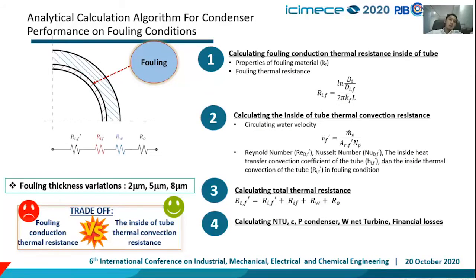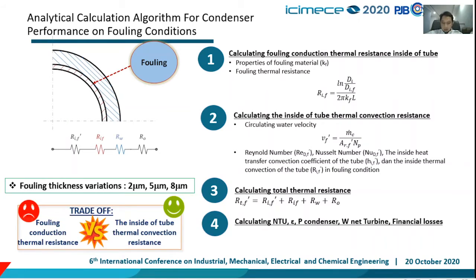This is the analytical calculation algorithm for condenser performance under fouling conditions. We use three fouling thickness variations: 2 micrometers, 5 micrometers, and 8 micrometers. On one hand, fouling conditions increase the conduction thermal resistance, but on the other hand, the inside-tube thermal convection resistance will decrease. These two opposing effects will be examined in this paper to find out which one is more significant to condenser performance.